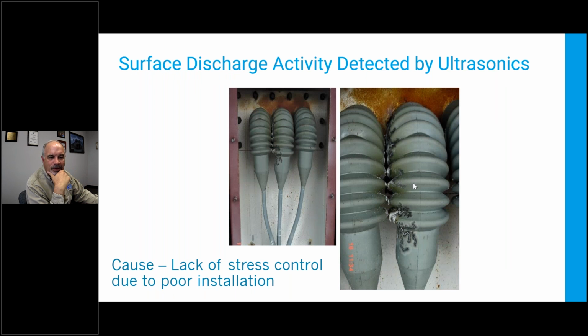Here is deploying the wrong parts for the job. There's nothing wrong with these boots. They're just not made to be this close together. By being this close together, we cause a field stress concentration, and we've got discharge. We've got tracking, white powder, and rust. All the bolts are rusty, and if I were able to zoom out in this picture, you'd see the bolts at the bottom of the cabinet are as clean and dry and non-rusty as can be. So that's a good indication. If you don't see anything else, why is it rusting?